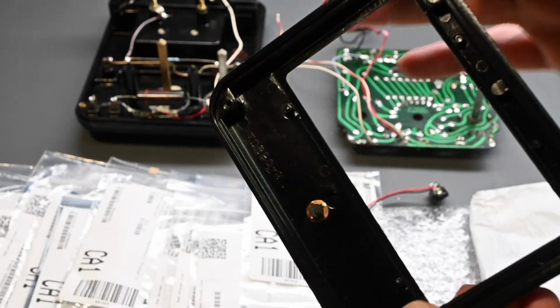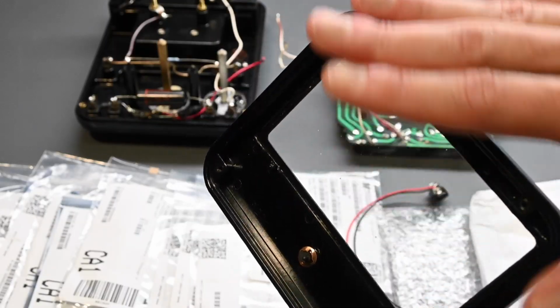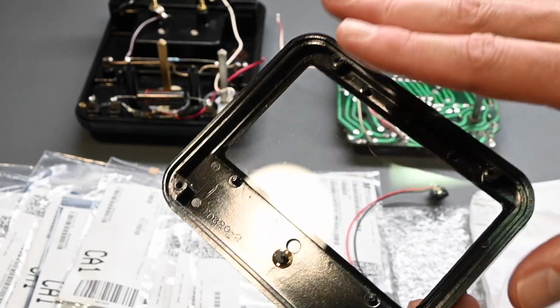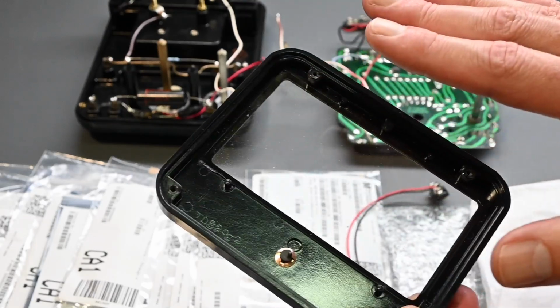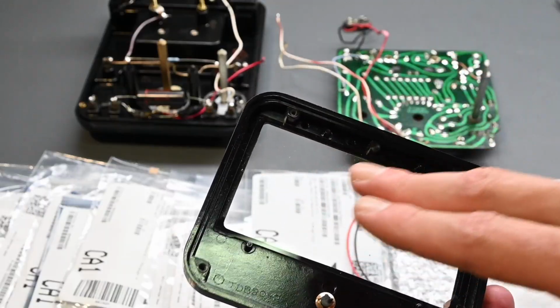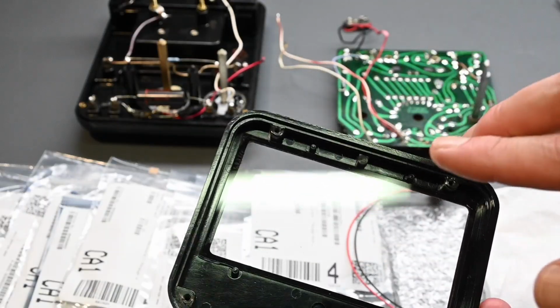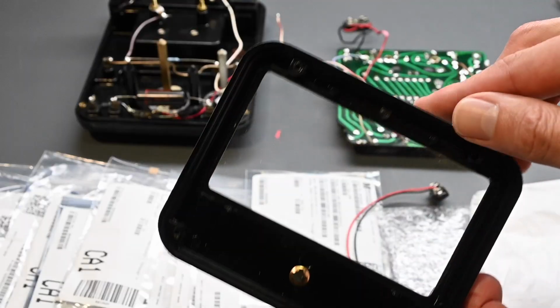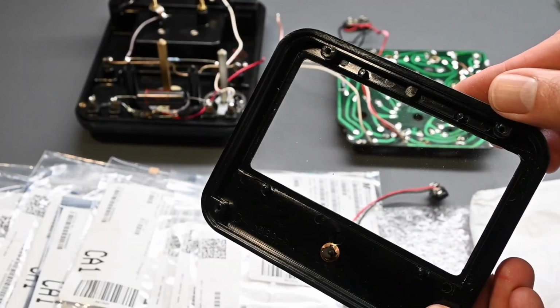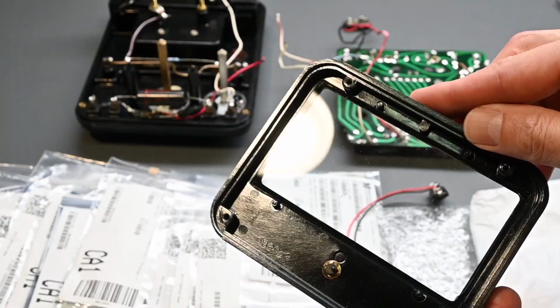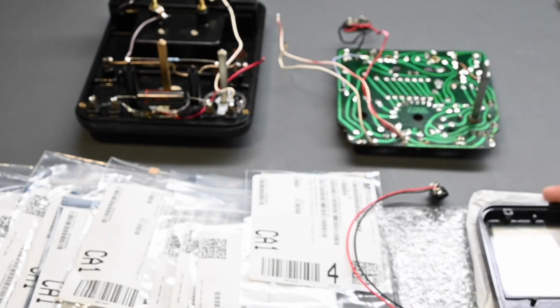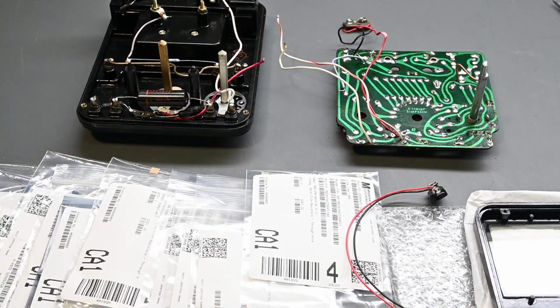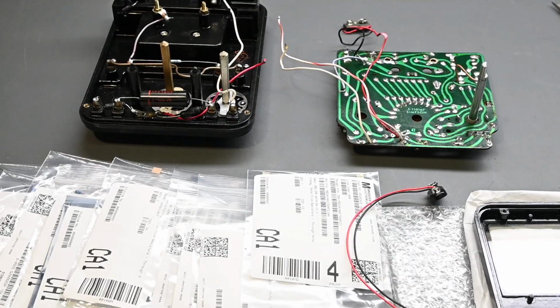And also, the glass that's in here, you have to coat this with an anti-static coating. If you don't do that, then a static charge can build up on this and it will affect the needle movement, and basically the needle in the meter movement will repel with the static charge that's on this glass. And you don't want that to happen, it'll affect the accuracy. So you have to just wipe this down with an anti-static cleaner. You can actually use a dryer sheet, something like that, or an electronics cleaner that's safe for plastics and things like that. That's a lot of times sold as like a dust-off type, dust repellent type cleaner. So I'll do that before I install that piece.